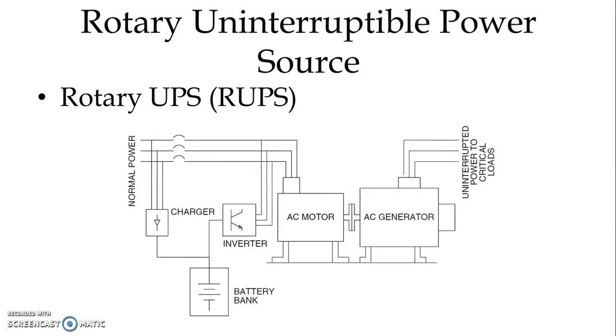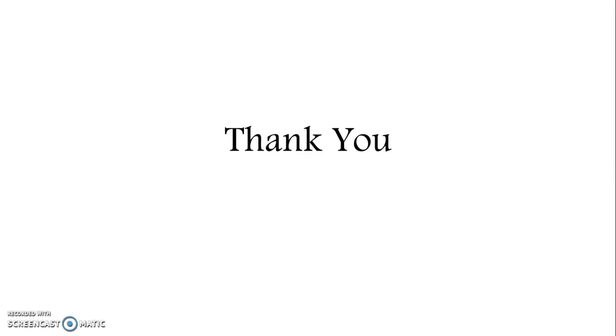We have another form of rotary UPS. Instead of using a diesel engine, sometimes we use a battery, and we use a rectifier to charge the battery. We use an inverter to convert DC power from the battery to AC power, and through the AC power we feed the AC motor in case normal power is lost. And through the AC generator, we have an uninterrupted power system available. So as long as the battery has stored power, we can convert that DC power into AC power and rotate our AC generator to maintain the source of AC power uninterrupted. So this way we can have an uninterruptible power system.